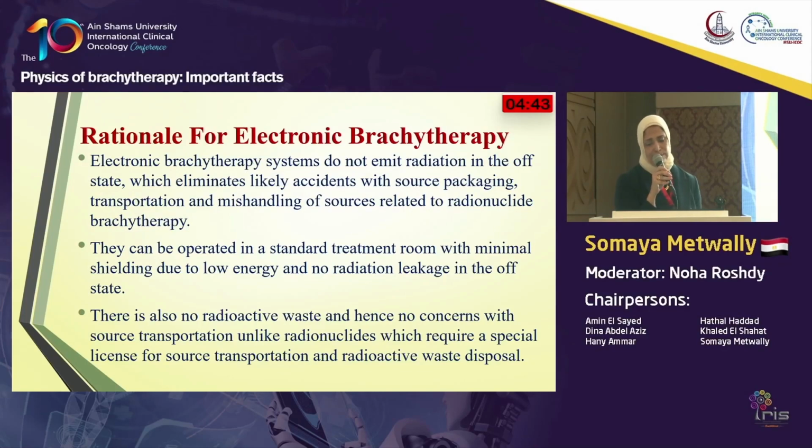Rationale for electronic brachytherapy. Electronic brachytherapy systems don't emit radiation in the off state, of course, because we have an X-ray tube inside the machine, which eliminates likely accidents with source packaging, transportation, and mishandling of source related to radionuclide brachytherapy.